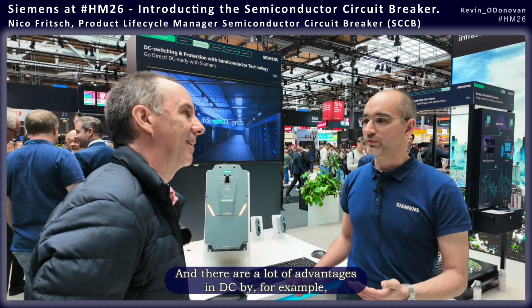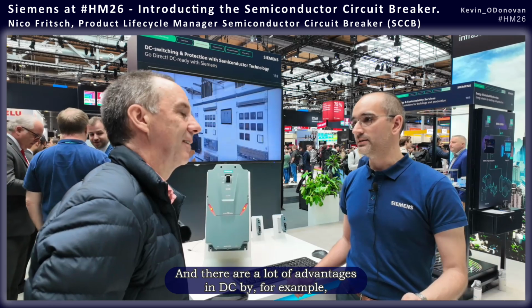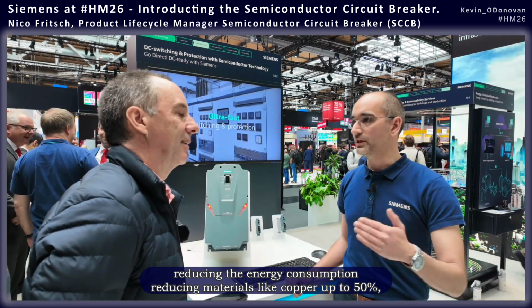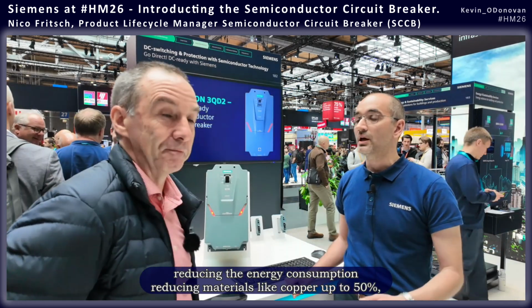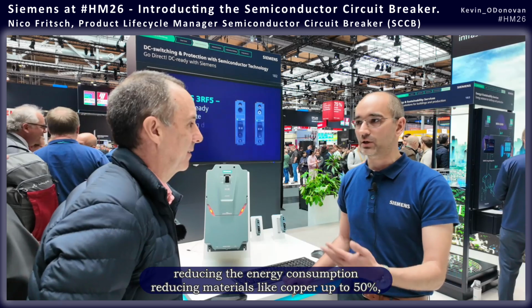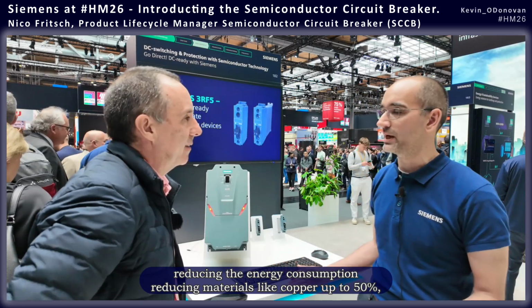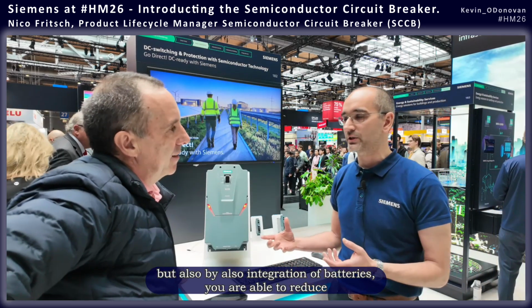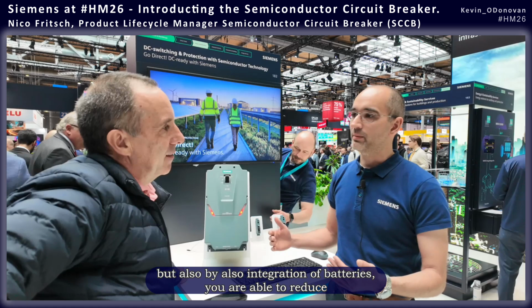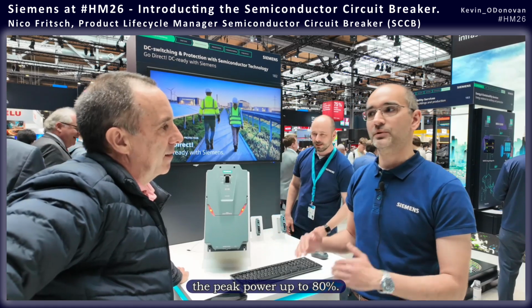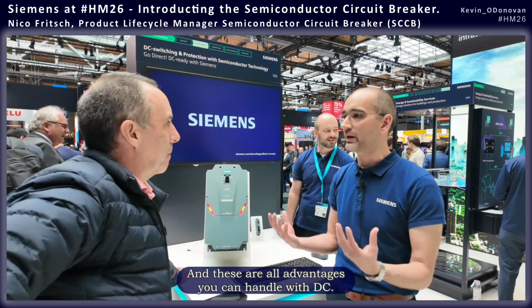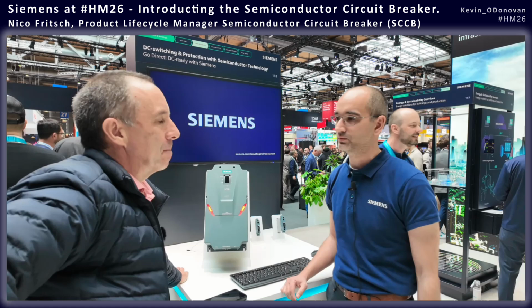There are a lot of advantages in DC, for example reducing the energy consumption, reducing materials like copper up to 50%, but also by integration of batteries you're able to reduce the peak power up to 80%. These are all advantages you can handle with DC.